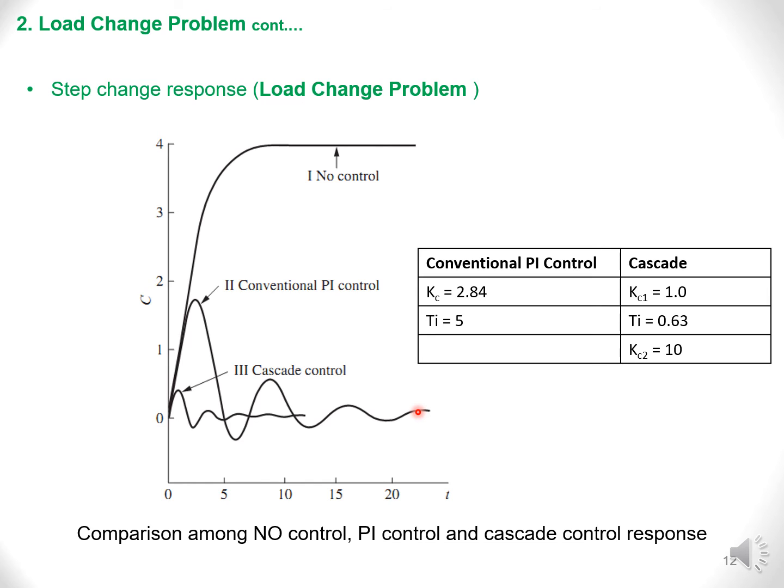So this is the advantage of having this sort of cascade control system that definitely makes the response go faster back to the set point, or to the new set point that we want for servo control just now, and also cuts down on the oscillation, which is very important when you have systems like we saw just now for the distillate control, temperature, coffee boiler control, and heat temperature control. We need it to go back quickly to the set point. Cannot afford a long time.